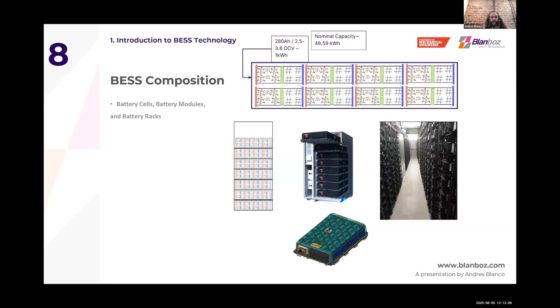A very important piece of equipment is your power conversion system, or PCS. PCS, for whatever reason, is the conventional name used for batteries, but it's pretty much the same converter or inverter used in the solar world. The only difference is that this has to be bidirectional because it's going to charge and discharge. We can have multiple levels of converters, and the more levels or bridges, the more efficient they are, but that also has an impact on price.